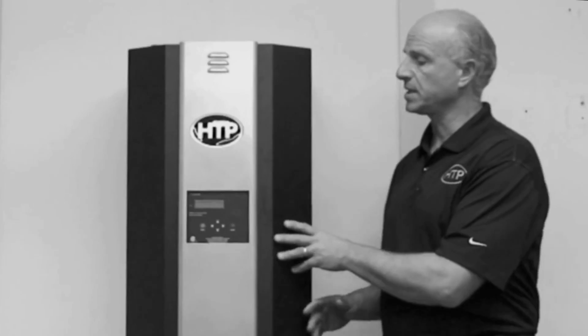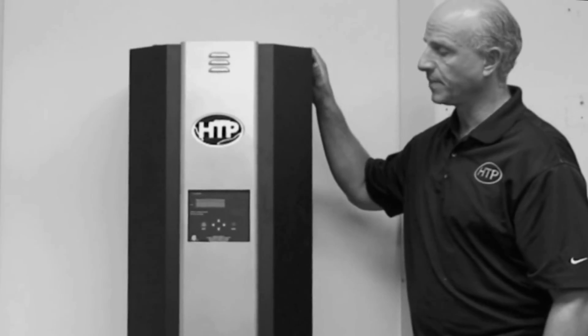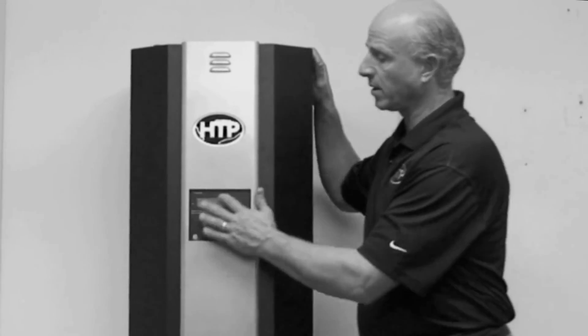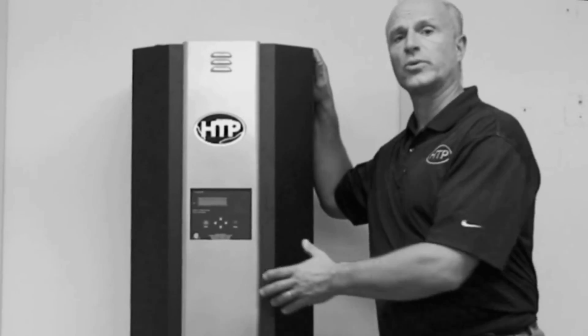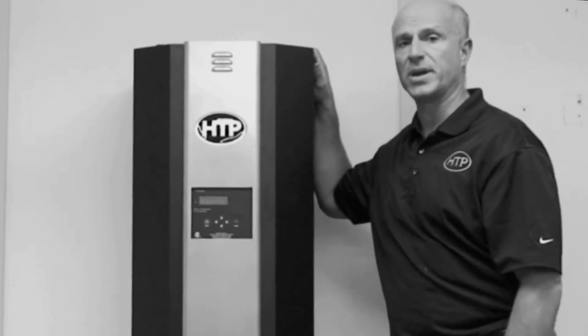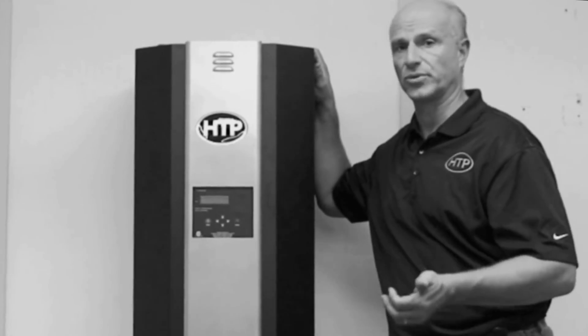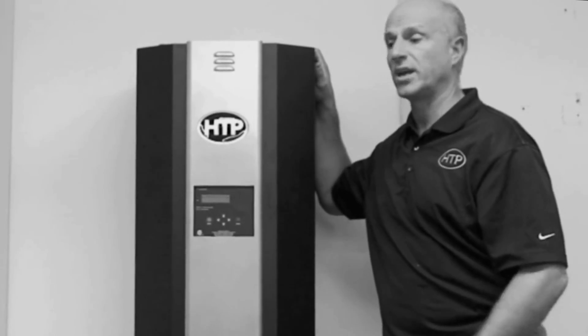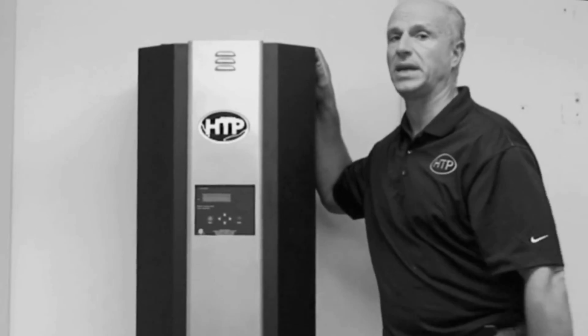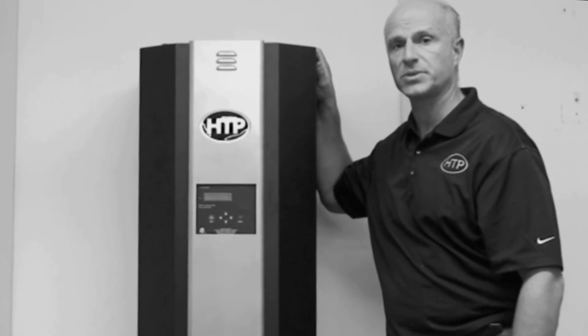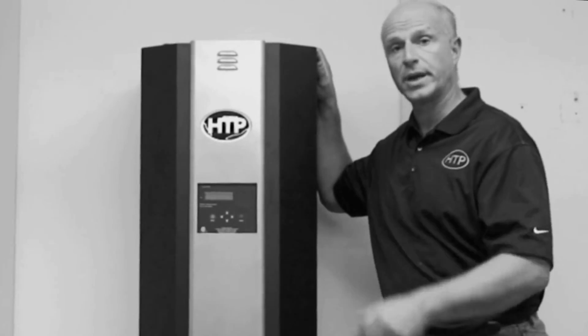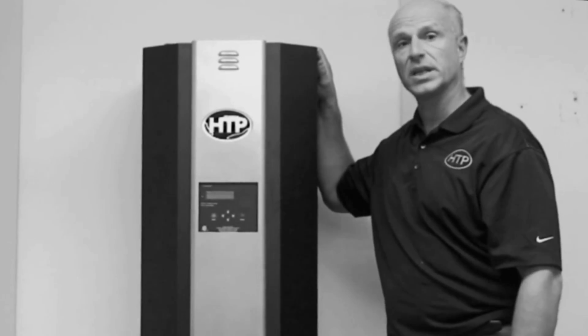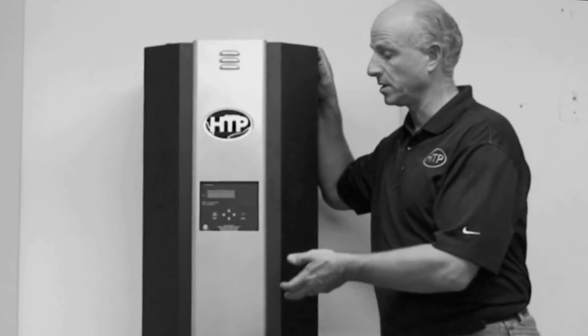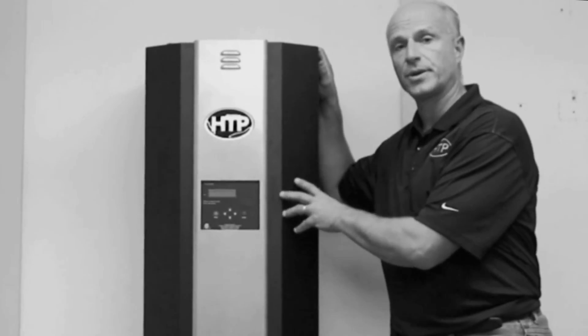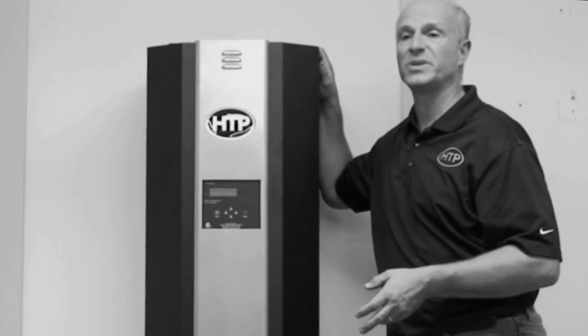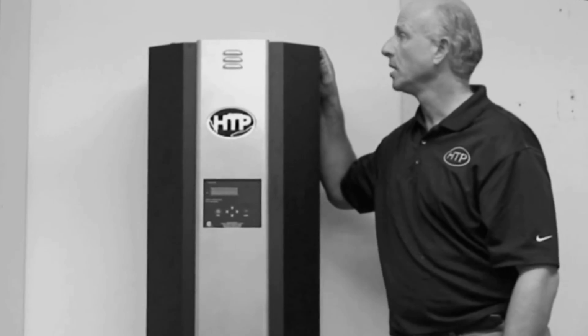The versatility of this system, being a wall-hung system, and the control panel that we have here, and the controller itself, we can set the system up in a number of different fashions. We can go for a reset with it. We can set up multiple boilers. We can do cascading up to 8 boilers for large commercial systems, which will give us greater turndown. The ease of installation and the amount of electrical draw, because we have some volume in this heat exchanger, allows for smaller pumps, which means less electrical usage.